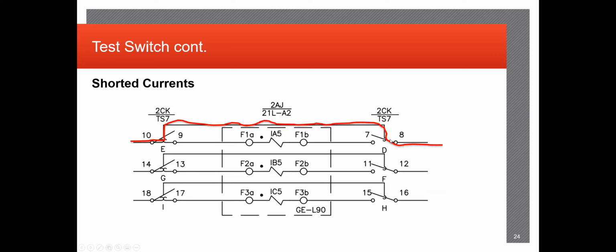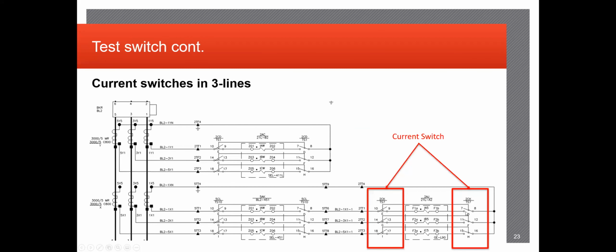This right here is identifying the shorted currents, meaning that if the test switches were to be open, it would be shorted actually across past the relay and through the test switch itself onto the next points. So you can identify them usually by these little hook switches here. I don't know if, yeah, these had them too.